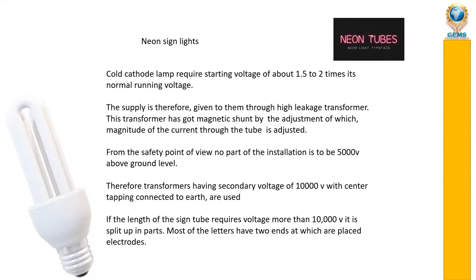If the length of the sign tube requires a voltage of more than 10,000 volts, it is split into parts, since above ground level only up to 5000 volts can be used. Each letter in a neon sign has two ends, and these two ends are connected to the electrodes, meaning each letter has two electrodes.